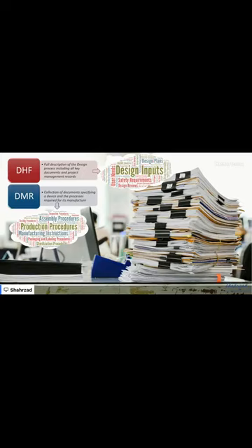Yes. So here we have DHF compared to DMR. A DHF is a design history file, and that's the full description of the design, including any key documentation and many project management reports. Okay. And DMR is really focusing on documentation around the process of manufacturing. I hope this is clearer now, because I tried to explain in different ways, and I hope that makes sense to you.